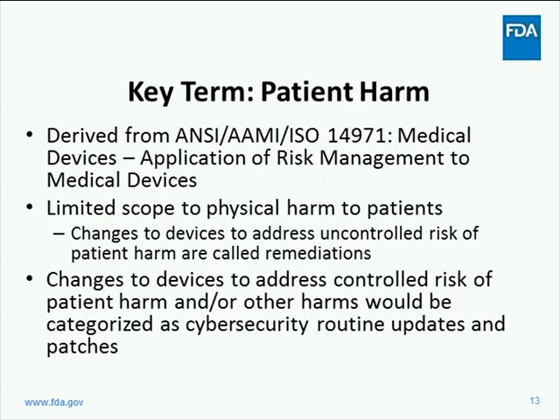Another key term in the final guidance is patient harm. The intent of introducing patient harm is twofold: to align with existing FDA and FDA-recognized standard definitions, and to appropriately scope vulnerabilities with the potential to affect safety and essential performance to those that could impact patients only. The assessment of risk of patient harm is key to determining appropriate manufacturer actions. Changes to address uncontrolled risk of patient harm are called remediations and are considered corrections. Changes to devices to address controlled risk of patient harm would be considered cybersecurity routine updates and patches.